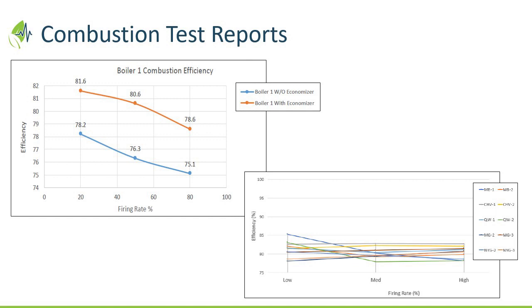You say, are we okay? Yeah, we're okay. Check it off, put it in the file. They're trying to tell you something. Every one of these test reports has a story to tell. You can see as firing rate goes up, efficiency goes down. You're trying to get more heat out of the gases and the stack gas temperature.